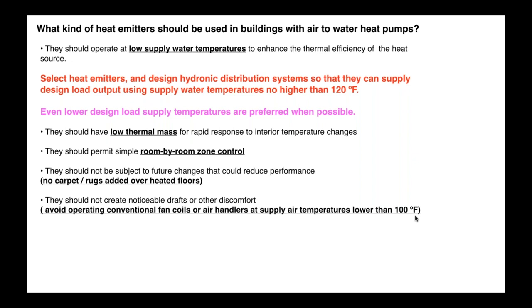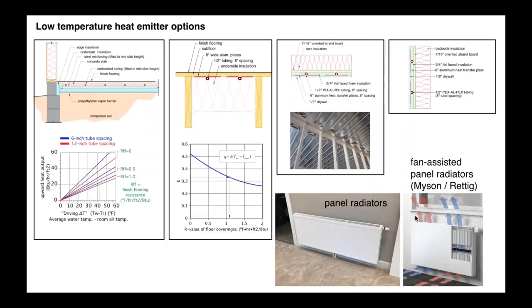Okay, if you're doing fan coils for heating, be careful. You don't want to do a deep reset on that water temperature because you're going to get complaints about cool air blowing out of the registers. So supply air temperature lower than about 100 degrees Fahrenheit and not well diffused into the room are going to potentially cause those complaints. So bottom line, low temperature, low mass, hydronic distribution systems are a good match. And again, in Hydronics 27, we go into more detail, but I just wanted to give you kind of a collage of what's possible here.